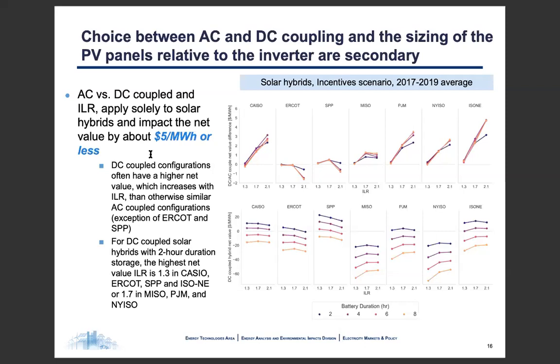In the top row of the figure, we plot the differences in net value between a solar DC coupled hybrid plant and the net value of the identical configuration, except with an AC coupling. And what we see is that with the exception of ERCOT and SPP that show negative values, the DC coupled configurations have a higher net value that increases with ILR, shown in the x-axis, than otherwise similar AC coupled configurations. So this is shown here as positive values in the figure. And DC coupling allows the battery to capture energy that would otherwise be clipped by the solar generator's AC inverter.